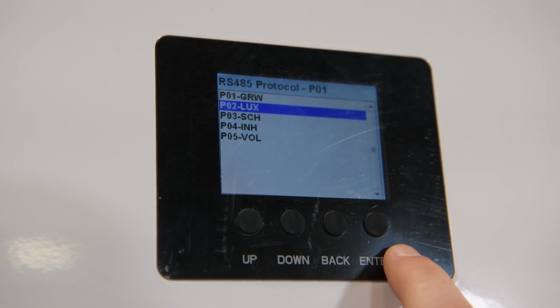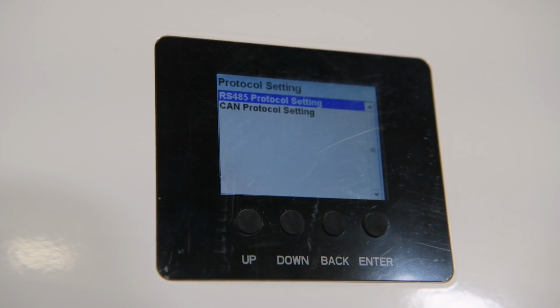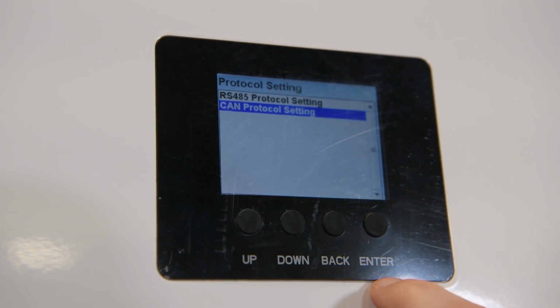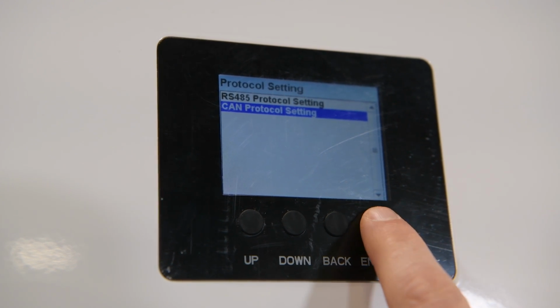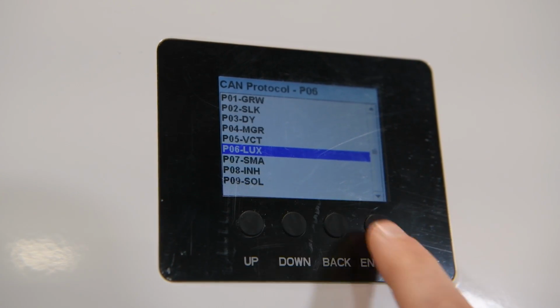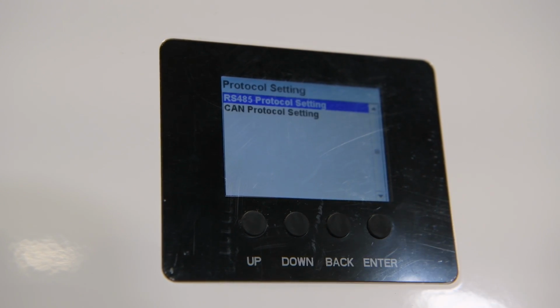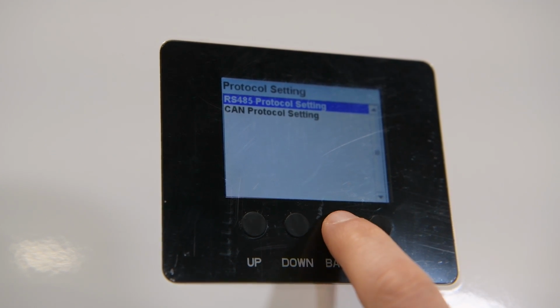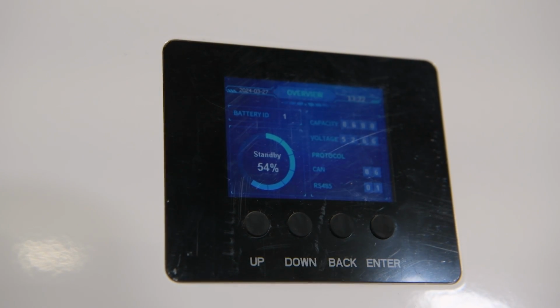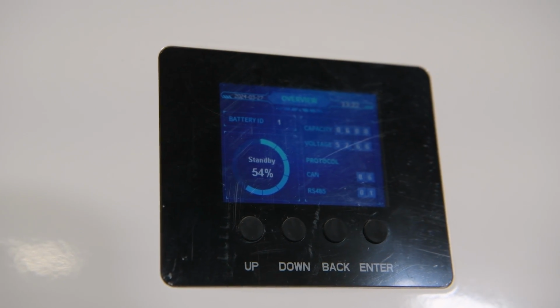The display will then return to the previous screen. We will go down and select Lux EG4 on the RS-485, press enter, then go into the CAN protocol and select Lux EG4 and press enter as well. This is only necessary to do once based on the way your inverter communicates.